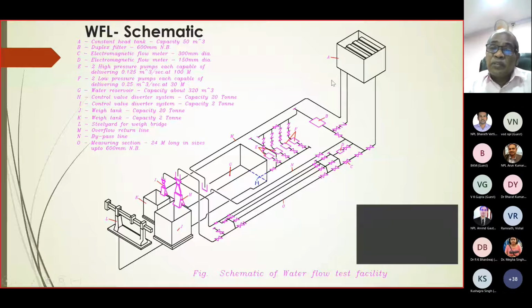We have a constant head tank also. Then the reference flow meters are electromagnetic flow meters. Here we are using the basic primary method, the gravimetric weighing method. That is the most accurate method for water flow measurement. If you look at this figure, these are all the pumps. Then it goes to the constant head tank. Coming to the test section, there are various test lines available. These are all the reference flow meters. Then the upstream control valves and downstream control valves. It goes to the diverter.